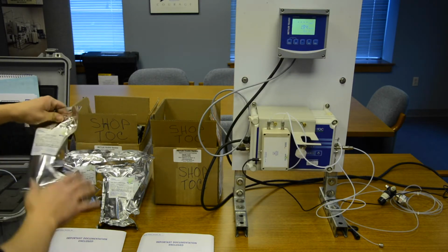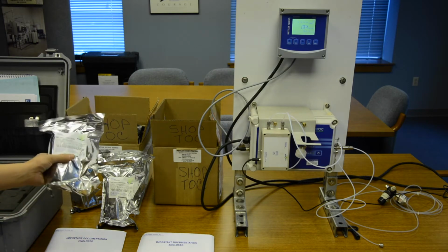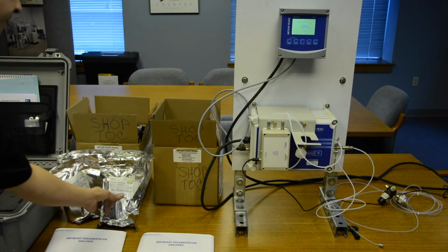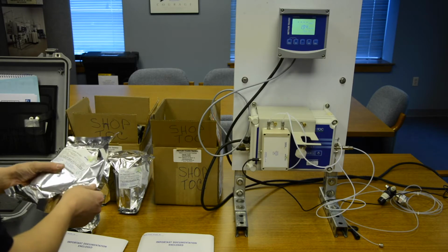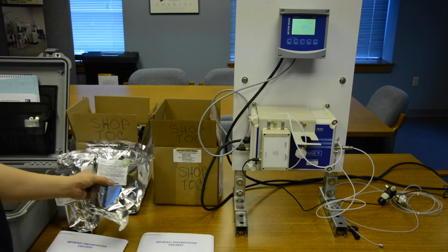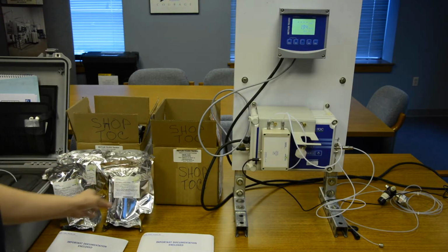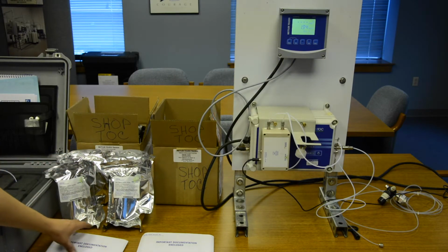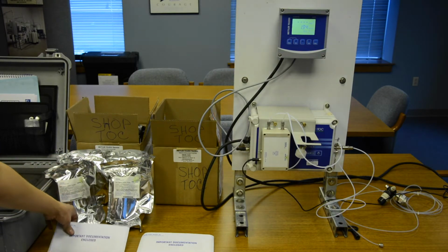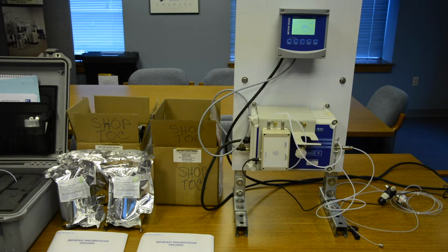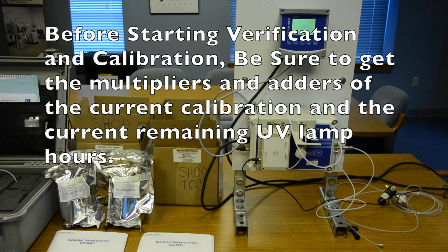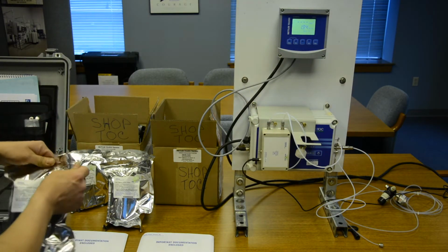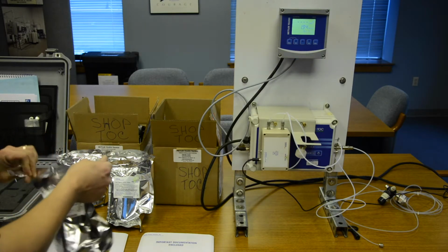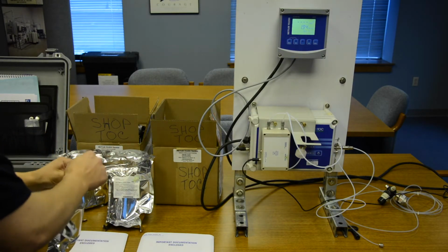The next one that we have is a 503 part per billion solution made of sucrose. And then we also have a 253 part per billion sucrose solution. And these are our 2 calibration solutions that we'll be using. And then you also have inside the certifications that are certifying the actual quality of the water from the lab that it was created in. So the first thing we're going to do is take the 500 part per billion calibration solution. It's actually 503 parts per billion. And we're going to open that up.